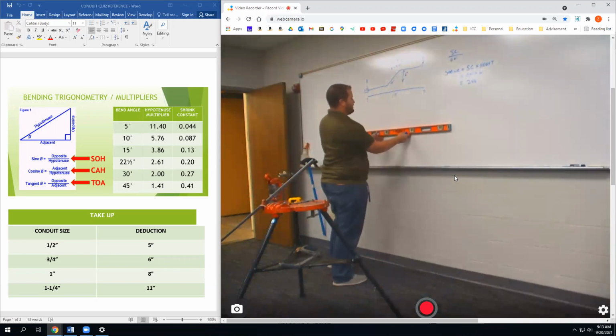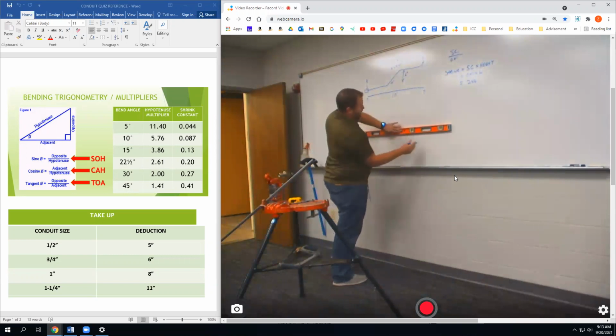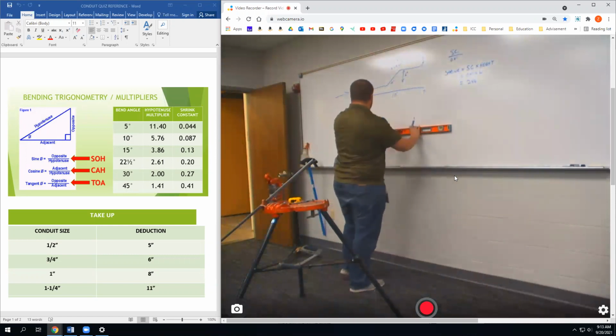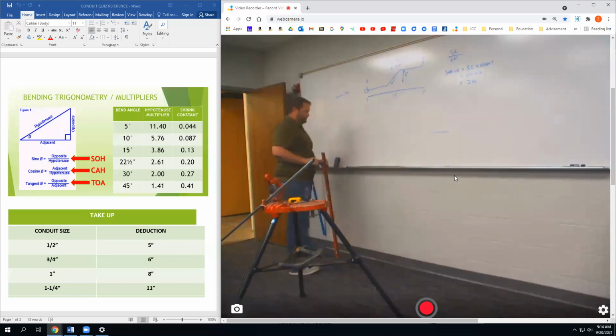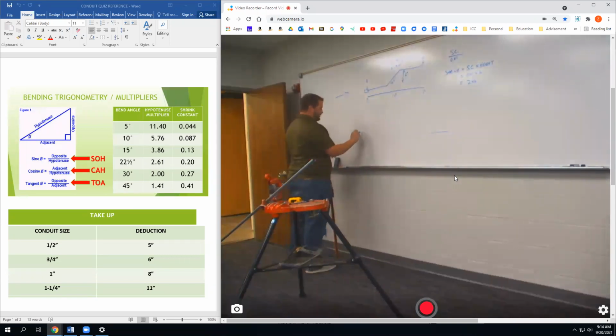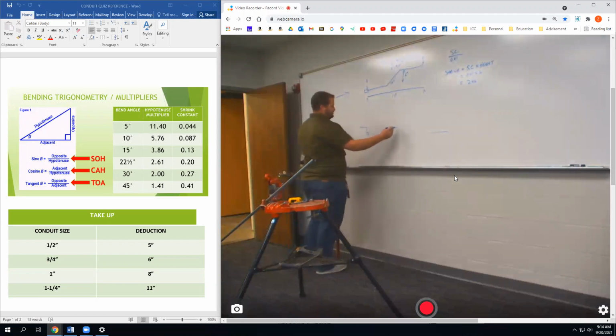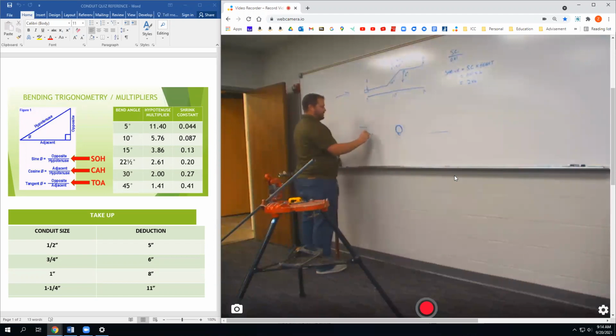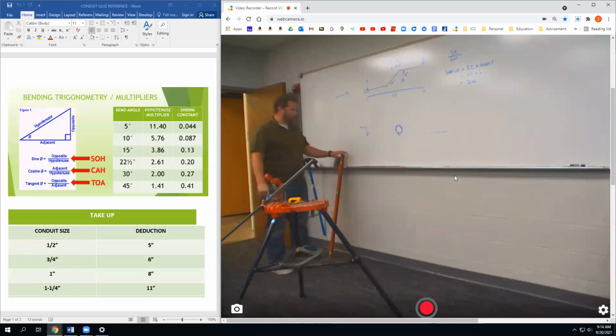The wall, one of your bends is going to look like this, and then you're going to have this trough here, the coupling sticking out. And then there's a pipe. It's actually on the Unistrut. So we need to go up and over this pipe with a 3-point saddle. So walk me through how to do that.